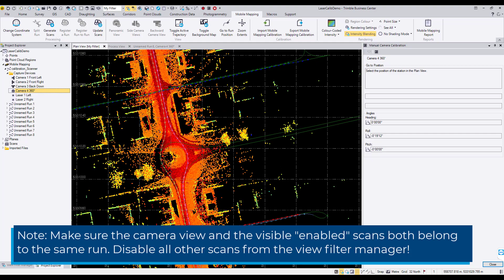The calibration values for the heading, pitch, and roll rotation angles can be manually modified in the Manual Camera Calibration dialog. In this example, there is a clear misalignment of the heading angle when overlaying the point cloud in the imagery. One option to adjust the calibration values is to simply enter new values in the heading, roll, and pitch fields. After entering a value, the view will update when another field is selected.